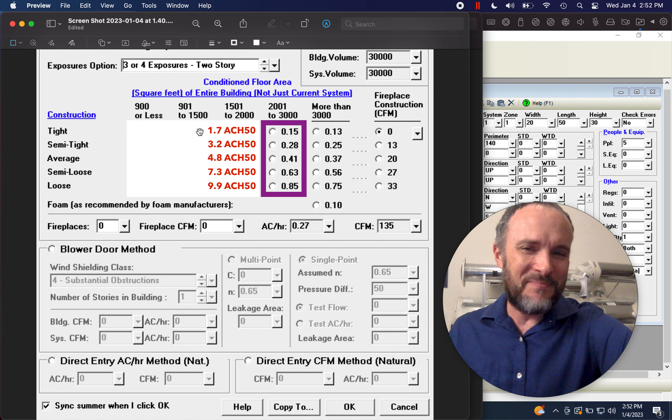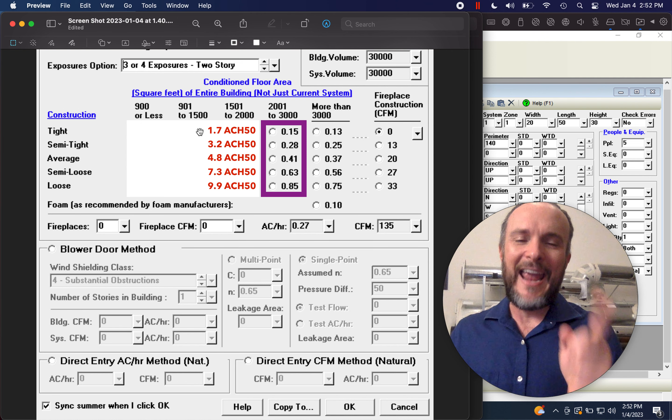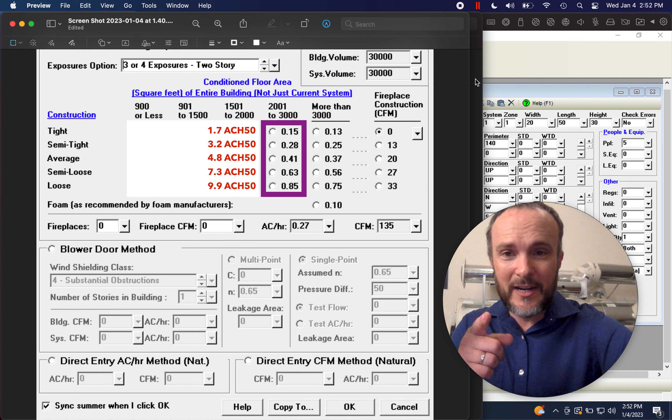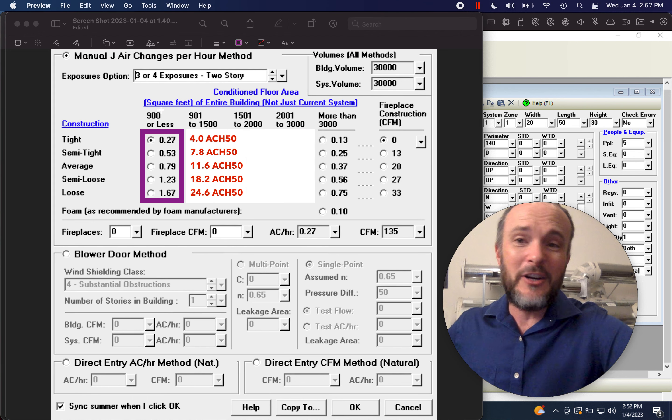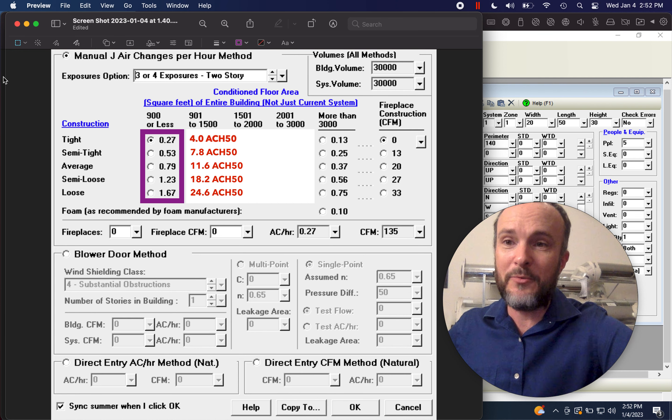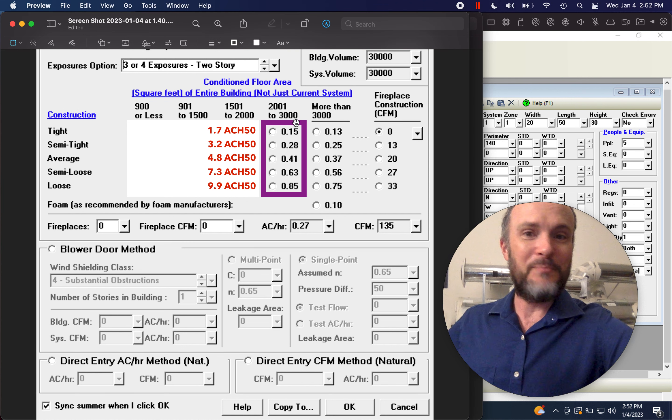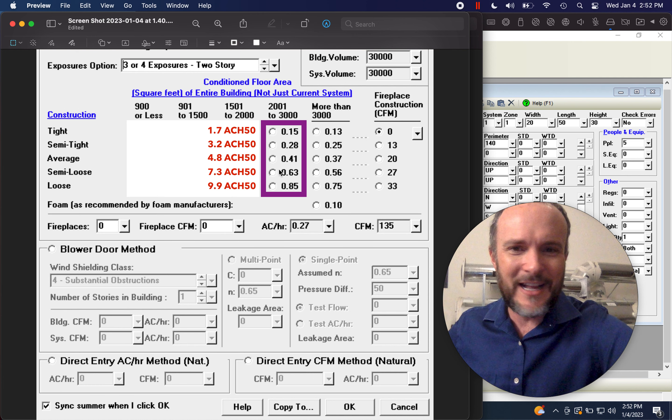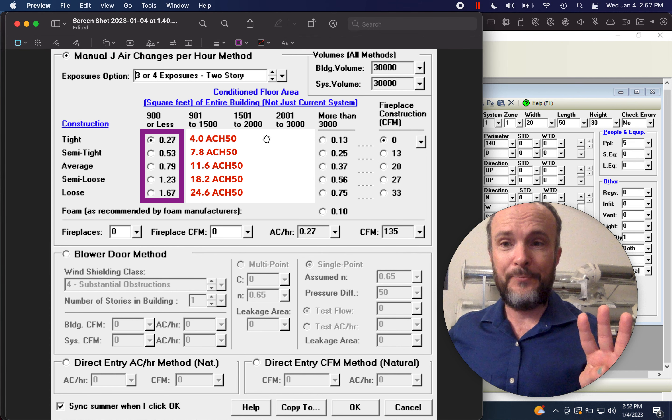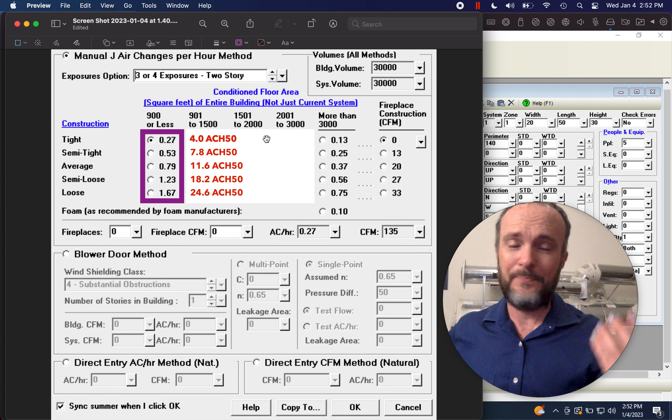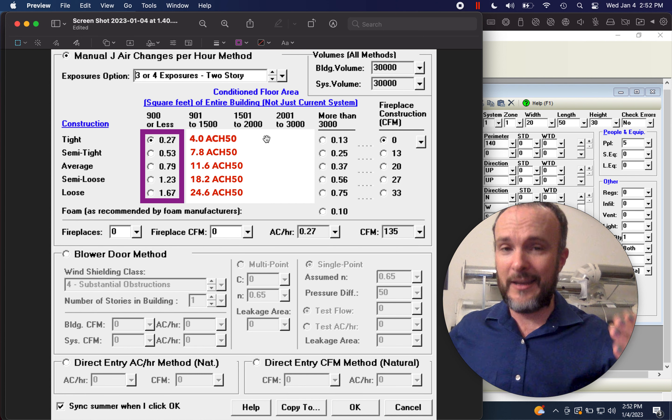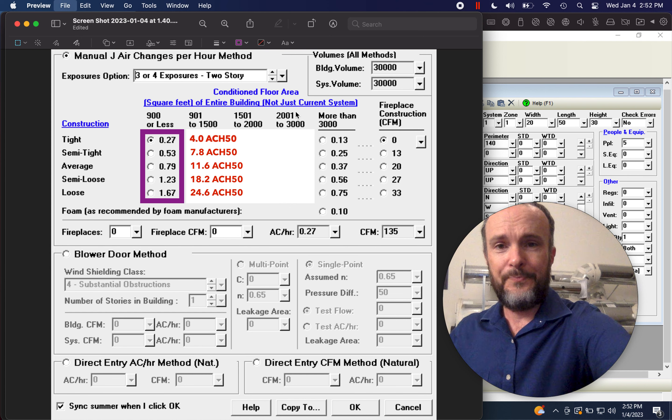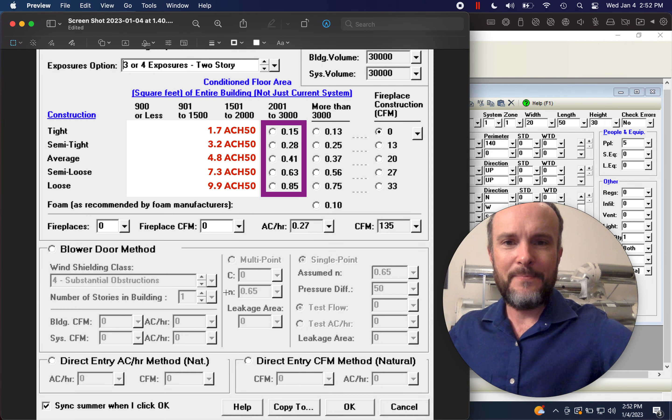So now we're either like grossly overestimating the air leakage on the tight side or grossly underestimating it potentially on really old homes that are really leaky on the loose side. And incidentally, one of the differences between elite and Wrightsoft is that elite makes you choose based on your square footage. And if you get this wrong, look at what happens. We started at 1.7 ACH 50. If we forget to move over to the right column, and by the way, there are two columns here. We got 3000 square feet. Do I pick the 2000, one to 3000 or the 3000 and up because they both include 3000. It's different values here. You can see that. So here we go, we start at four ACH 50 for the tightest home that I can get on this table. We go all the way to 24.6. So that's what happens if you are running elite and you're not thinking clearly, and you're trying to use these defaults, which you shouldn't be doing in the first place.